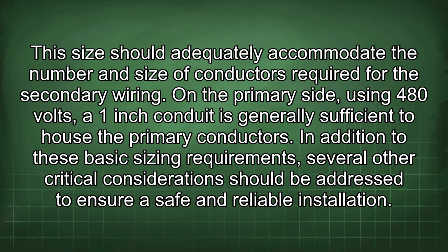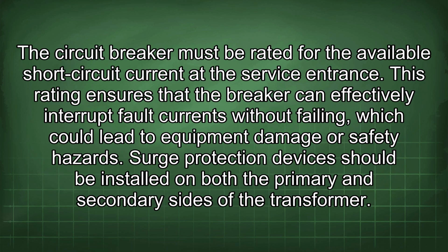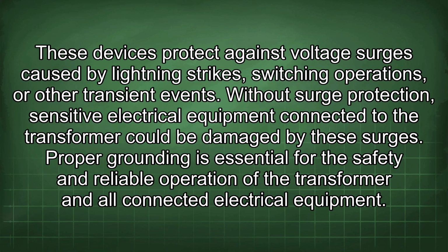In addition to these basic sizing requirements, several other critical considerations should be addressed to ensure a safe and reliable installation. The circuit breaker must be rated for the available short circuit current at the service entrance. This rating ensures that the breaker can effectively interrupt fault currents without failing, which could lead to equipment damage or safety hazards. Surge protection devices should be installed on both the primary and secondary sides of the transformer. These devices protect against voltage surges caused by lightning strikes, switching operations, or other transient events. Without surge protection, sensitive electrical equipment connected to the transformer could be damaged by these surges.